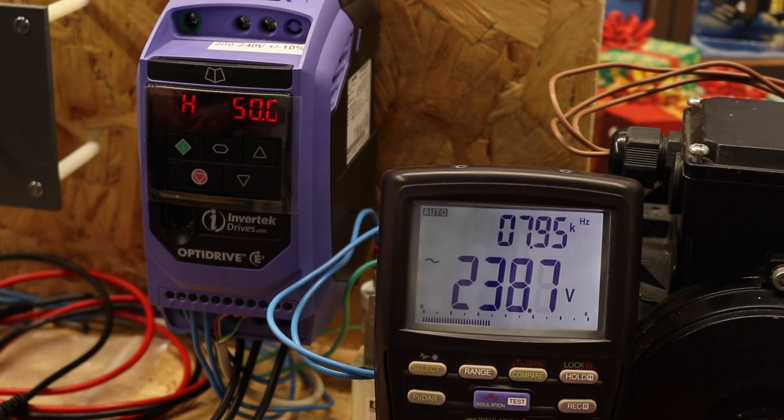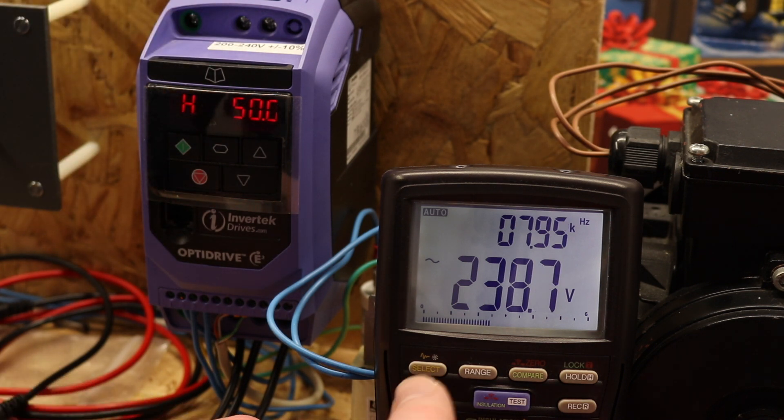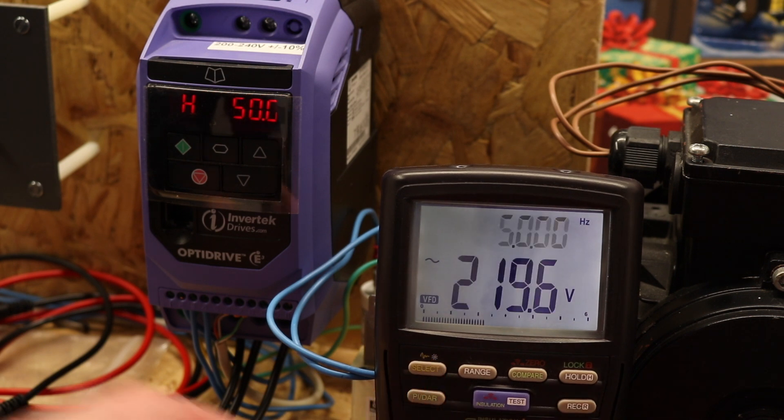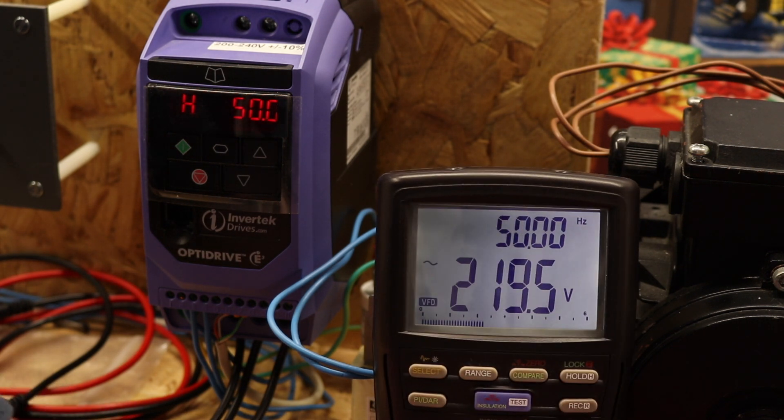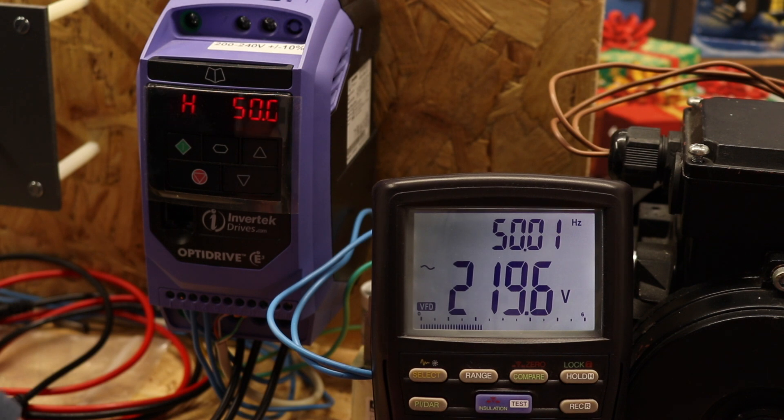The next meter is the Brymen BM877 — another insulation multimeter with true RMS and a VFD mode. In standard mode it reads 238.8 volts at 7.95 kHz — very much the fundamental frequency of the inverter. If I hit the button for VFD mode, you can see we drop down to 219.5 volts at 50.01 Hz — totally accurate, no problems with that one whatsoever.